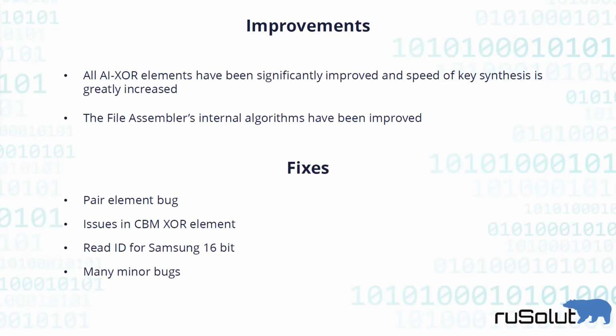Previously, in case you pressed the read memory chips button, VNR was testing multiple configurations. So it tests the voltage and so on. In this update, we added yet another mode, and this mode is prepared particularly for these Samsung chips which are using 16 bits. Previously, you wouldn't be able to read the ID using the normal ONFI mode. Now VNR will tell you that this chip is using Samsung pinout and 16 bits.